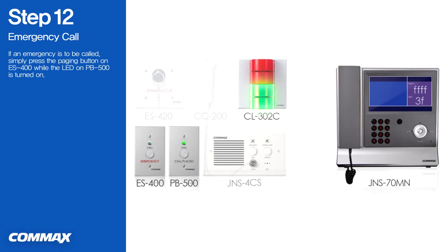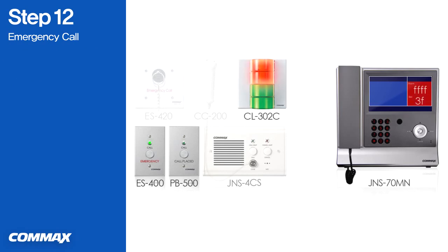If an emergency is to be called again, after checking the status of the patient, please press the paging button on ES400. It is important to check the LED on PB500 is on when you press the paging button on ES400. As the button on ES400 is pressed, the green LED on ES400 is turned on, and red lamp of CL302C starts blinking. An emergency notice is to be displayed on the screen of JNS70MN.